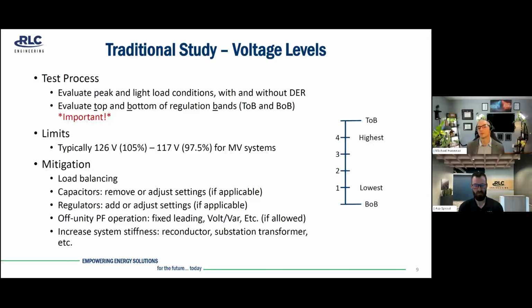What we've often found was the system impact study was run without the top and bottom of regulation band considerations. And when they were looking at it in the field, it just happened to be operating at a higher point within that regulation band, and it was missed. So it tends to have to be kind of go back, see what adjustments need to be made in order to secure the case so that they can actually go back and interconnect reliably.